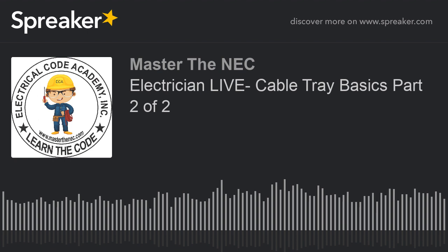All right. Next, let's look at what the deal is when you have a combination. So what if I have multiconductor and single conductor cables in the same application for ampacity? Okay, well, it doesn't get more confusing, but it's just something that you have to think about. We're going to touch on it because you could very easily have multiconductor configurations in the tray, as we saw earlier in 392.22, but also single conductor cables in there as well. So how will we address the ampacities on that? All right, the first way to think about this is to take each one of them individually.